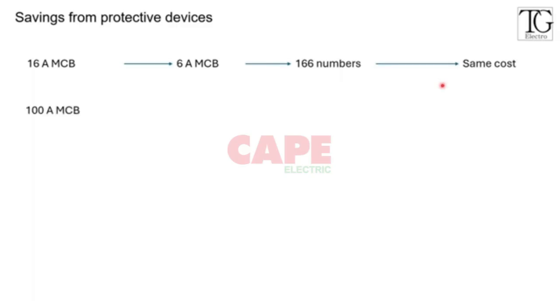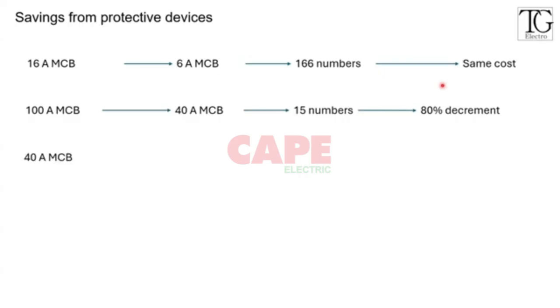Now they have also used 100 amps MCBs. We have changed them to 40 amps MCBs, which is close to 15 numbers. The decrease in cost is approximately 80 percent when going from 100 amps to 40 amps MCBs. Then we decreased to a 16 amps MCB for that project, which is close to 30 numbers, a 20% decrement.